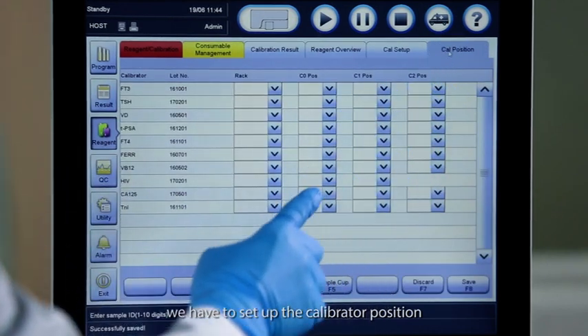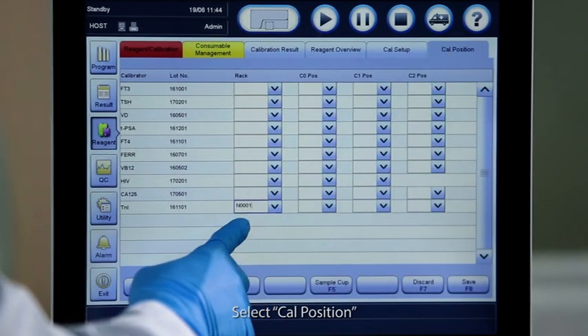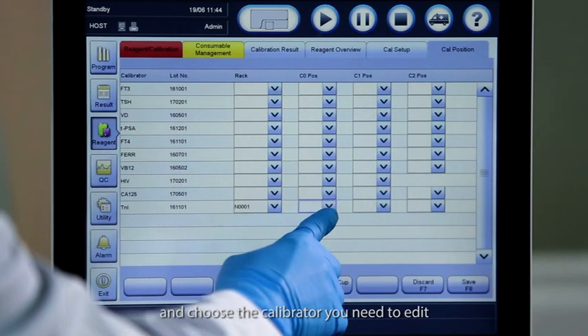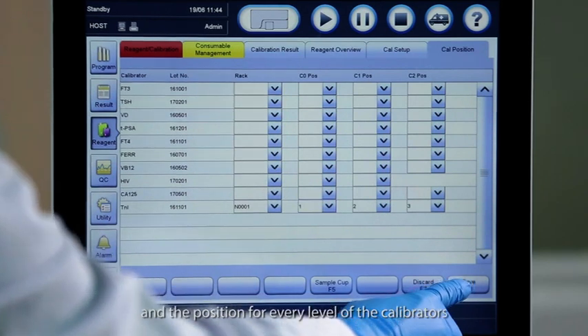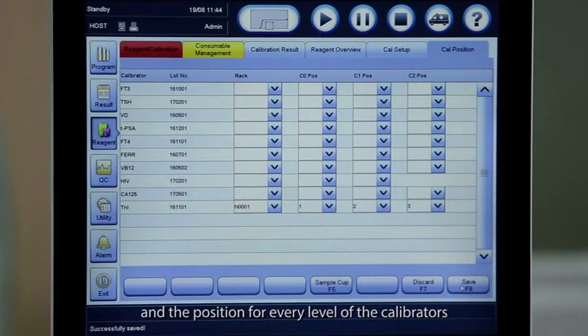After finishing this, we have to set up the calibrator position. Select cal position and choose the calibrator you need to edit. Choose a rack number or lane number and the position for every level of the calibrators.